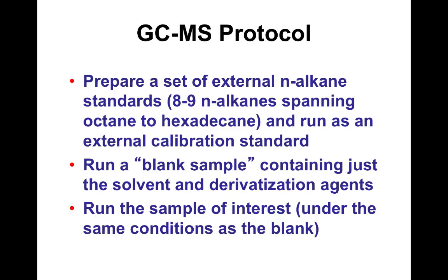So if you're going to do GCMS spectral deconvolution, there's a few things you have to do. The first thing you have to do is run a set of standards. And they can range from octane to hexadecane. These are alkane standards. And these can serve as your calibration standards, not only for intensity, but also for retention. So that's your external standard, the calibration standard, to help with quantitation and retention.